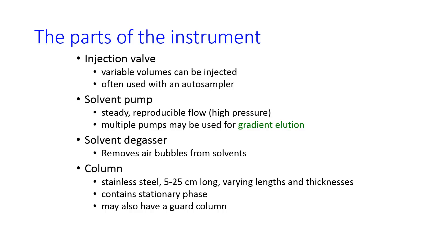And then we have the column. The columns are about 20 centimeters long, maybe a little longer, in contrast to GC columns, which are meters long. They contain a packed stationary phase. They may also have a guard column, which is shorter and not as good at separating things. The purpose of the guard column is to take out any big impurities that would damage the main column. And then finally, we have a detector.